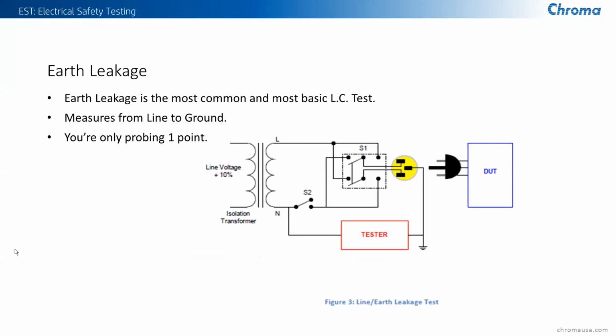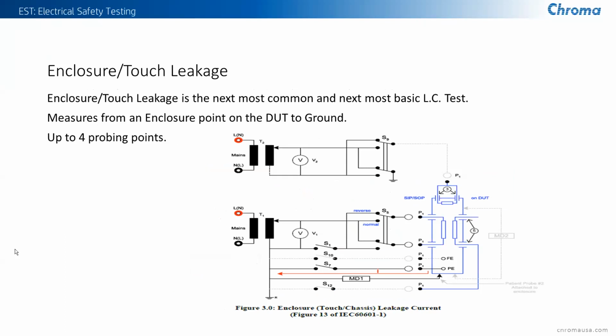Earth leakage also is a test that is performed. This is the most basic leakage current test. It looks to see whether any current is flowing through ground that could pass through the operator and cause a shock hazard. Enclosure touch leakage is where, if an operator places his hand on a conductive part of the device, such as a metal enclosure or chassis, he will not be exposed to a shock hazard.